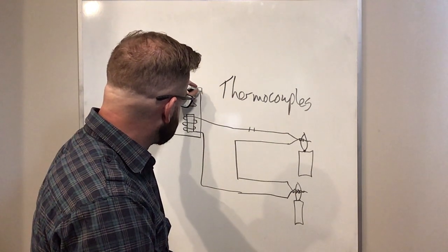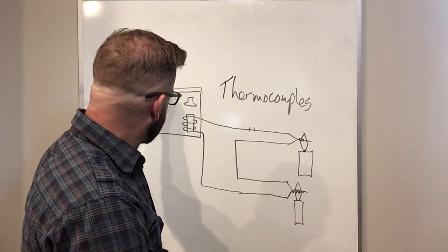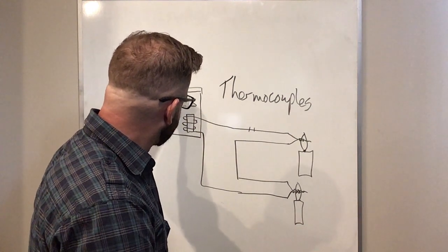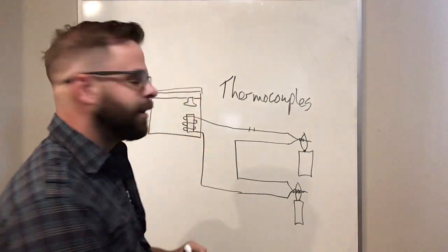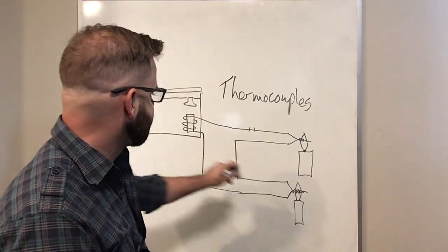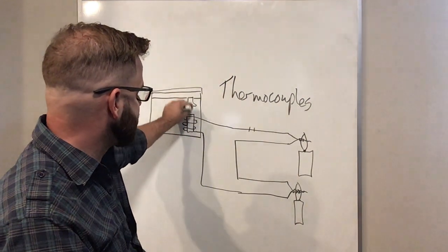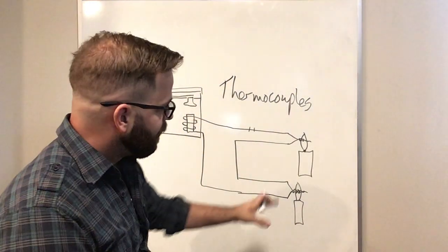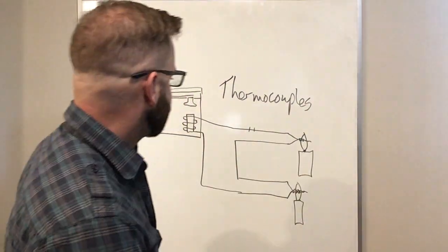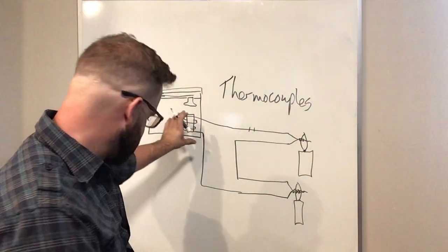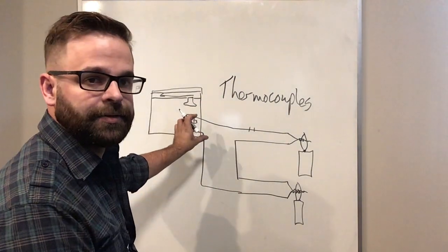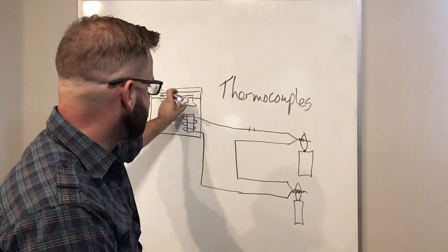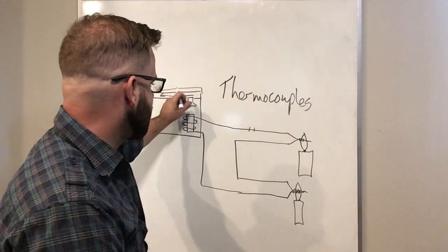Let's say that this is the flow for gas through from one side to the other. I'll just draw one of the valves here. And when I produce a flame, I create an electromagnet that pulls that plunger down so the gas can flow through. But when the flame ends up turning off, that de-energizes that solenoid, and this valve is obviously a piece of metal, and it ends up popping back up.